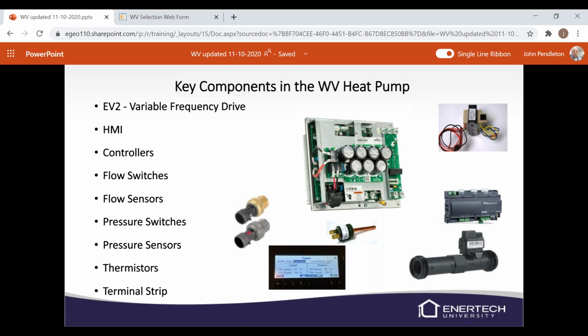There is a removable terminal strip. It's a green strip in the middle top of the unit in the control box. And that's basically where all your calls will come into. And you can remove that and jumper the unit. The wiring coming into the terminal strip are dry contacts. There's no power there. It's just a contact closure that completes the circuit. So if you're at the unit and you don't want to jack around with the thermostat or the aquastat to get it to run, you can pull that terminal strip and just put a jumper on it. A Y1 and Y1C call is a low heat call. It's like a radiant call. If you were to jumper Y1 to Y1C with just a little wire, the unit will come right on, or it should. Let's put it that way.